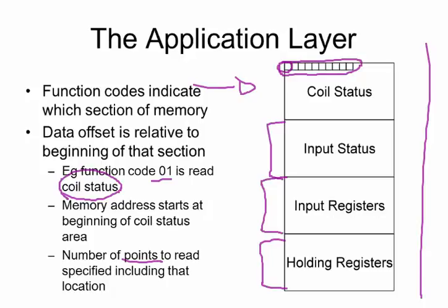holding registers. So where you see the addressing of 30,000-ish and 40,000-ish, it's referring to specific memory locations as originally defined in a Modicon PLC in 1970. So this is why some of the addressing looks a bit weird. You don't have to stick to those numbers. You can use anything you like, but by convention, most people will go with those sorts of addressings.